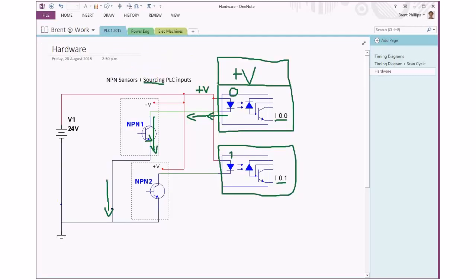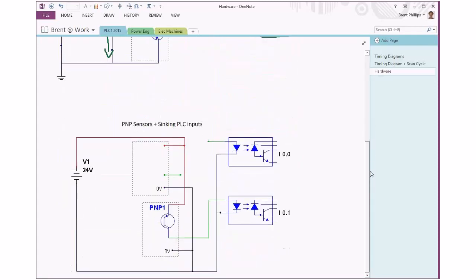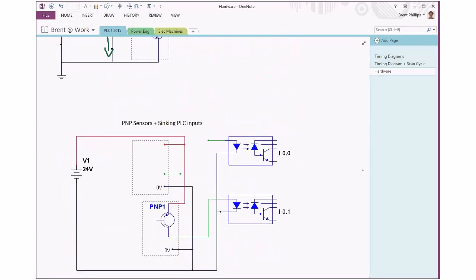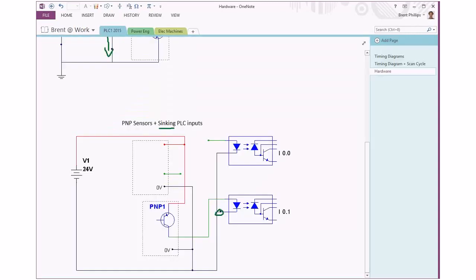So that's one way of distinguishing - any sourcing PLC input is going to have this positive voltage common. Whereas if we're looking at the opposite type down here, our sinking PLC input, the common connection that's shown here is a negative common.